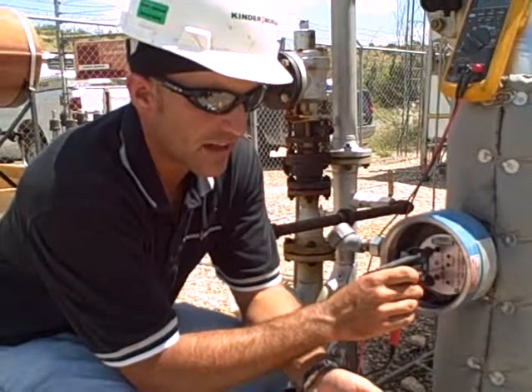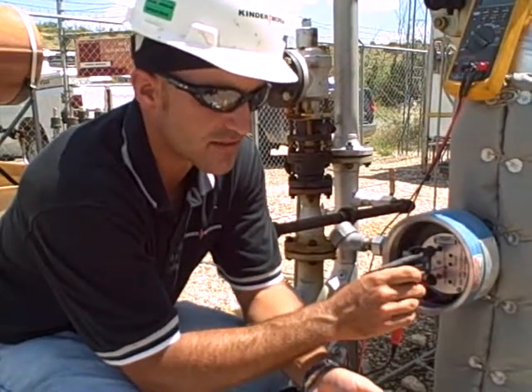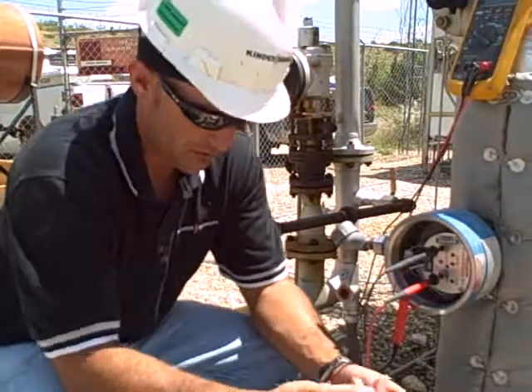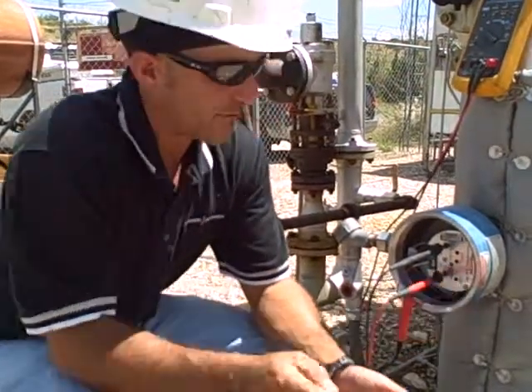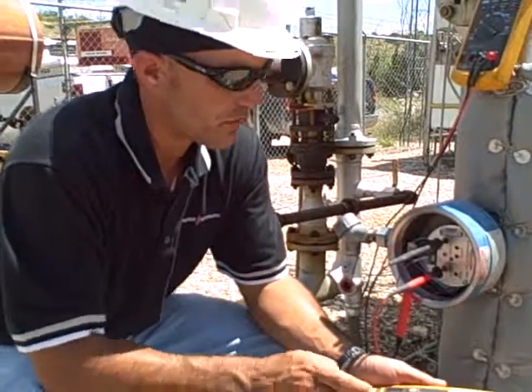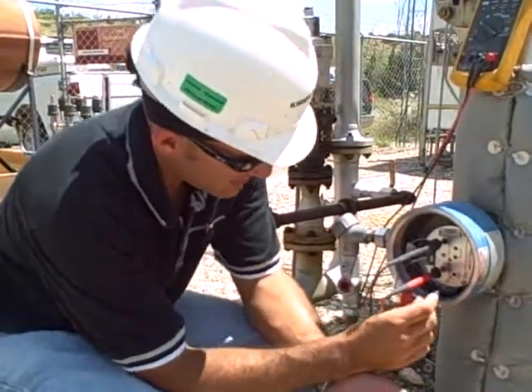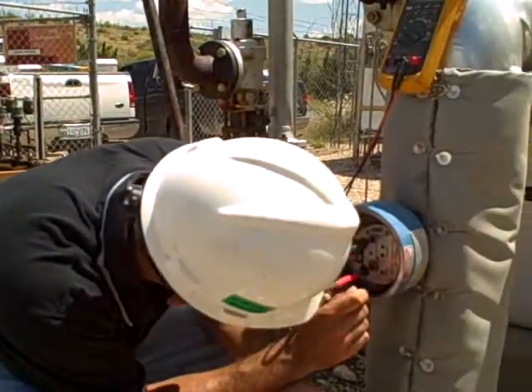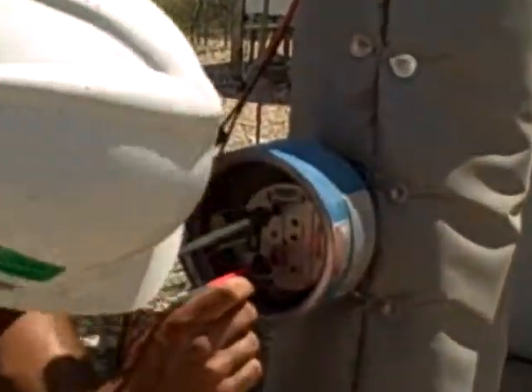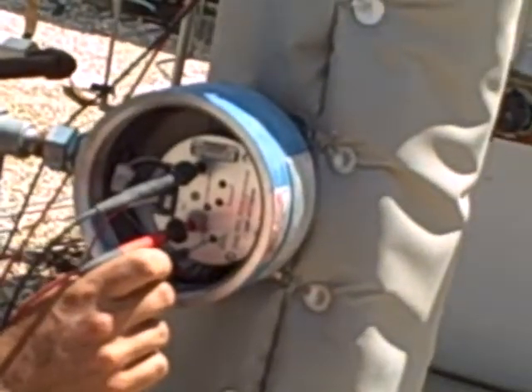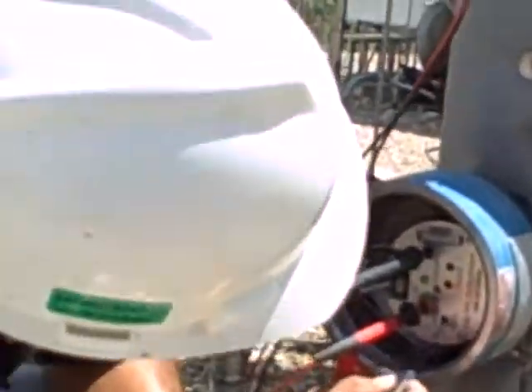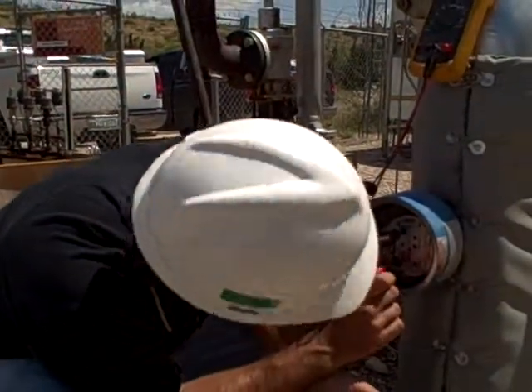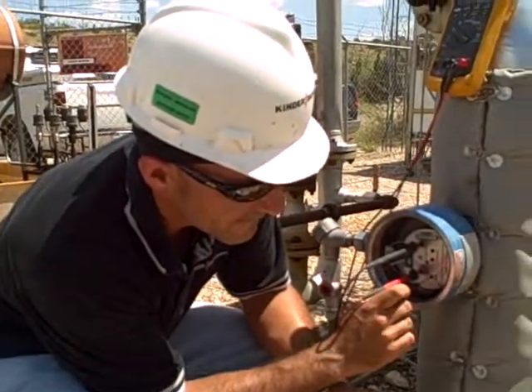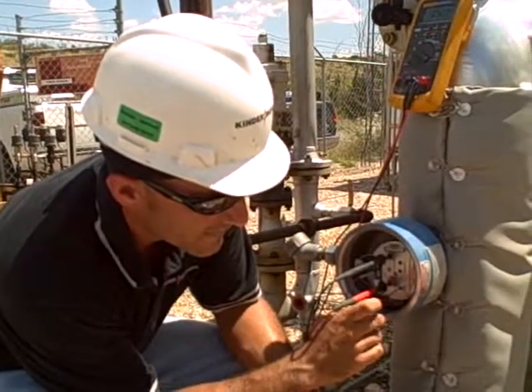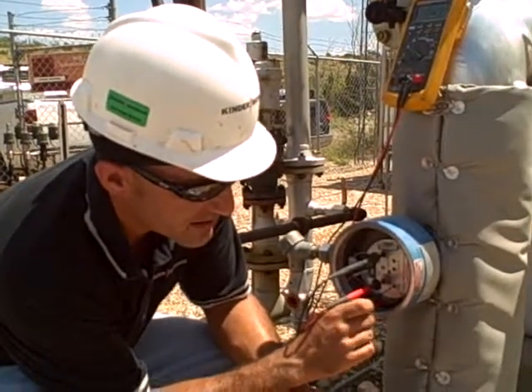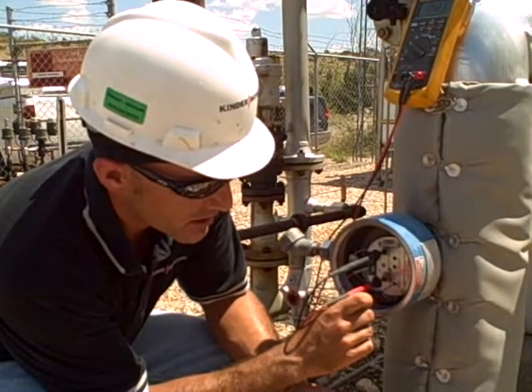Okay, I got it at 2.9%, which is close enough, plus or minus 3%. Oh, it's 3%. Okay. So then I'm going to go back to my reference, and I'm going to check my reference on my 4 to 20 milliamps. I use the same adjustment screw, the output span, as I did for the voltage. I'm going to turn that to make it 100%. I got it at 98%, and right there's 100%.